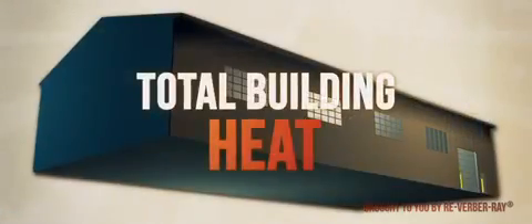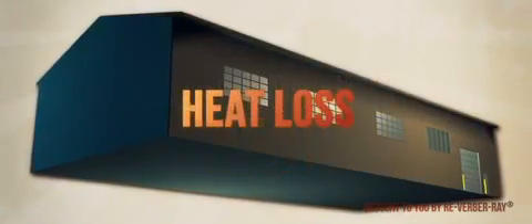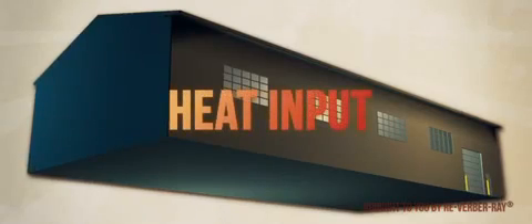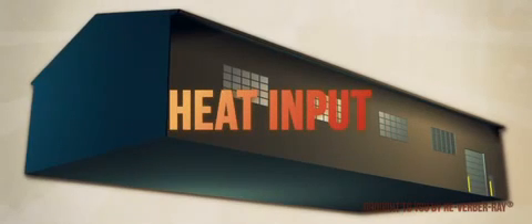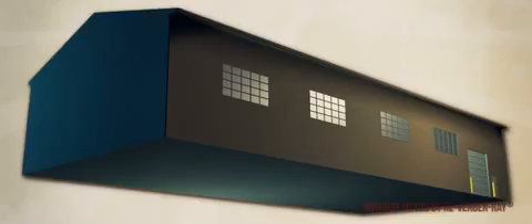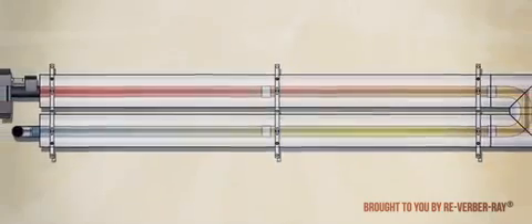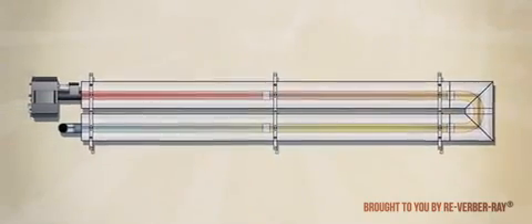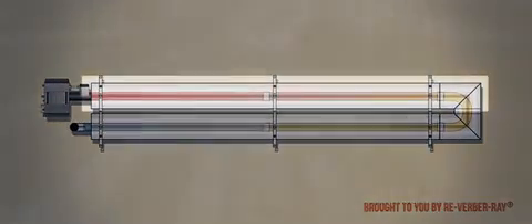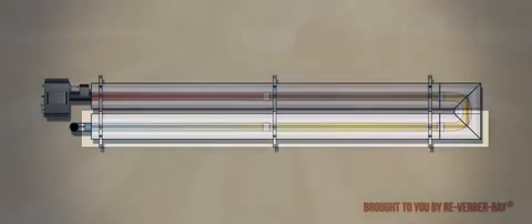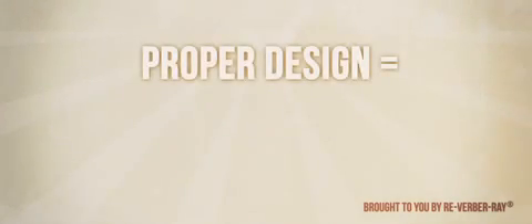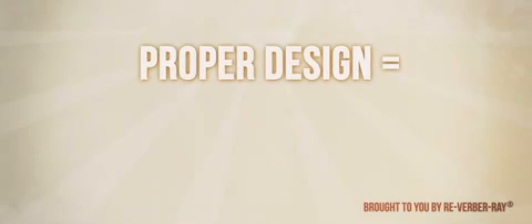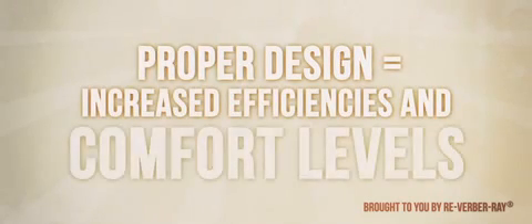When designing for total building heat, the concern is to replace heat loss with heat input. To accomplish this, it's best to place heaters in the most uniform pattern possible. U-shaped heaters are often the best solution when heating people or when tackling a spot heat application. By design, a U-tube will place the hotter tube directly adjacent to the cooler tube for optimal comfort levels. Proper model selection and good layout practices will result in increased efficiencies and comfort levels.